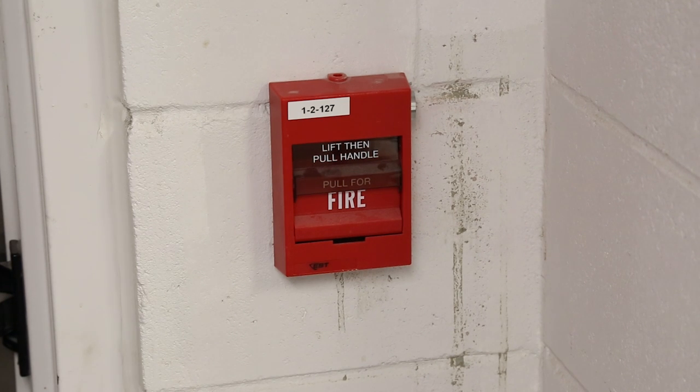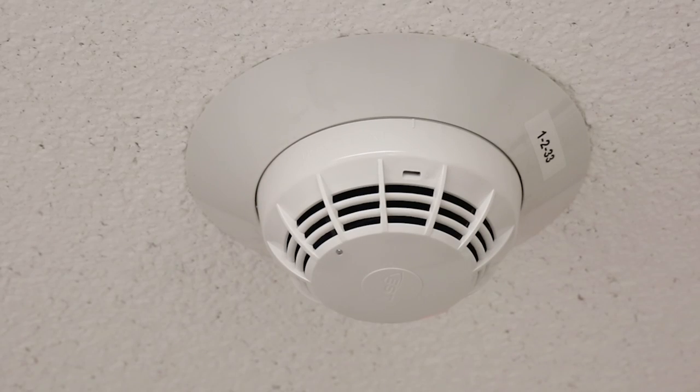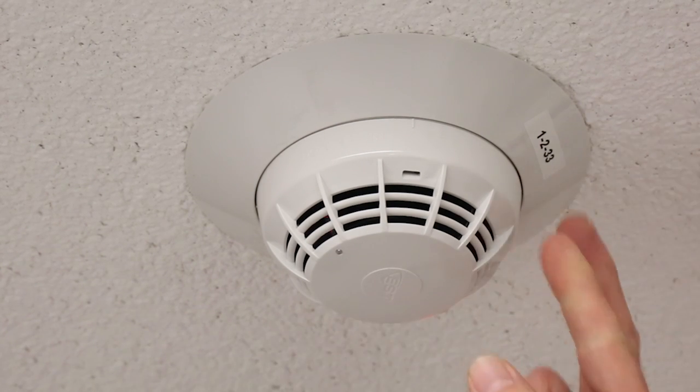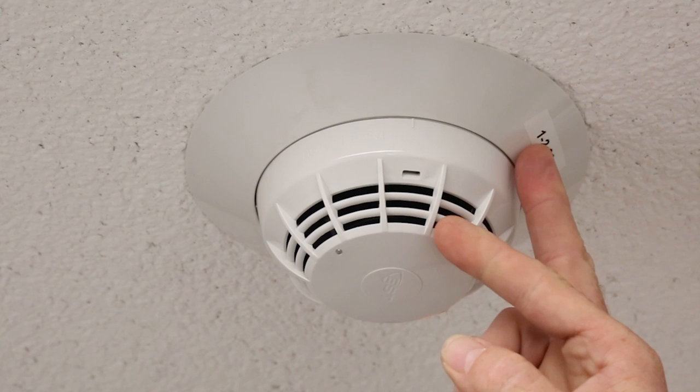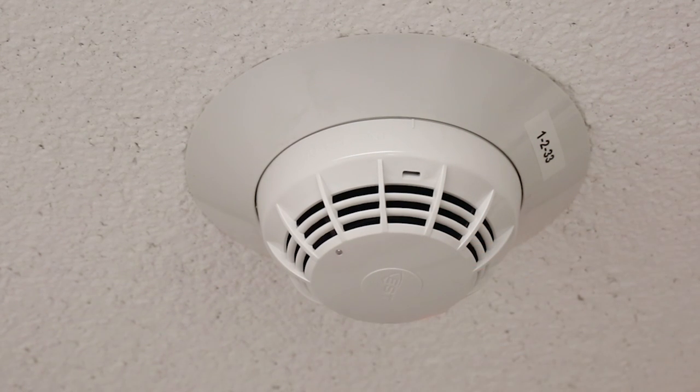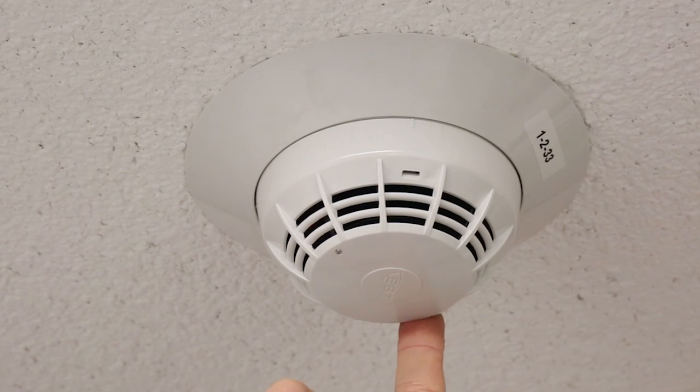And that's it. Like we talked about before, if its smoke alarm is basically an alarm condition, it'll tell you the exact location. There is a sticker on here that shows you the panel number, that's card number and device number. Right here there's an LED, I don't know if you can see it on the camera, but if it's flashing red like that, that's the one that's picked, okay? Normal condition would be flashing green when it's polling, but this indicates that it's an alarm condition. And that's about it.